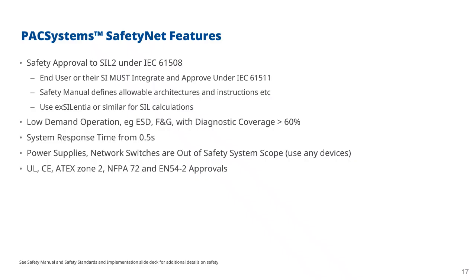Now, I mentioned that network switches are out of the safety system scope, so are power supplies. So you can use any suitable devices. The plan is that the system, if there is any failure, will shut down to a safe state. So you might want to choose components which are more reliable and industrialized than standard components, but we don't actually include those in our safety certificate.